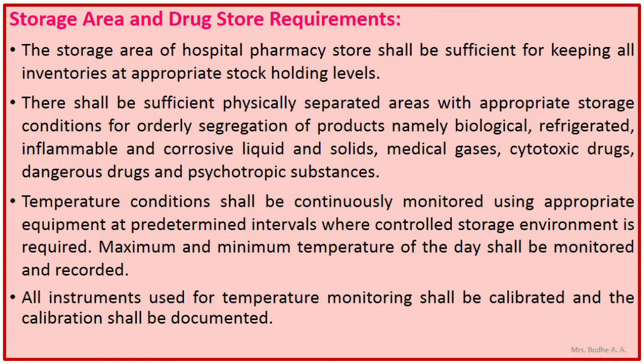Temperature conditions shall be continuously monitored using appropriate equipment at predetermined intervals where controlled storage environment is required. Maximum and minimum temperature of the day shall be monitored and recorded. All instruments used for temperature monitoring shall be calibrated and the calibration shall be documented. Let us see the image of segregation of products.